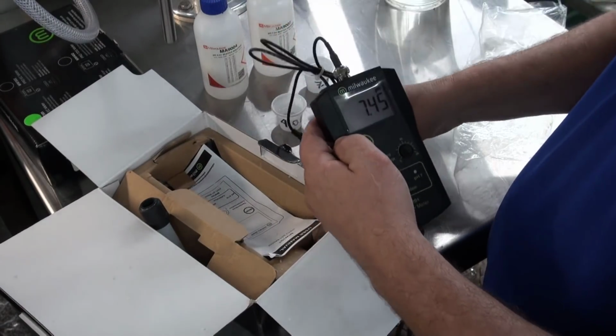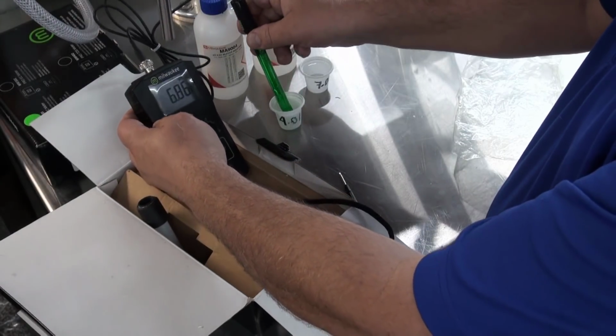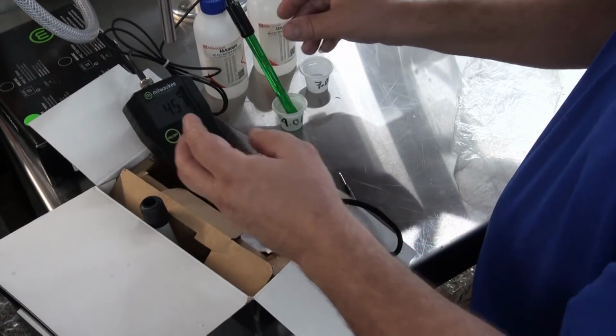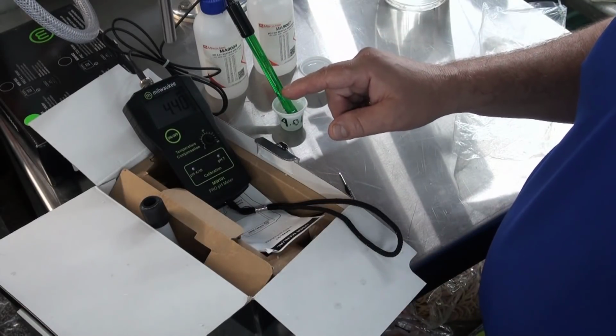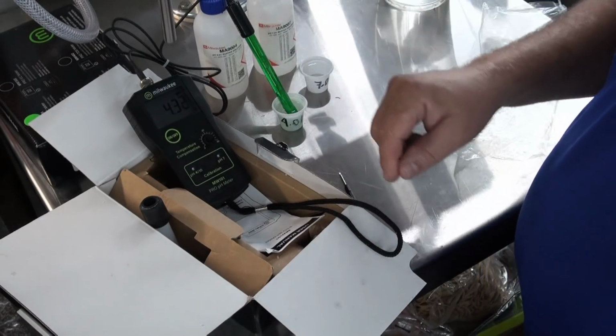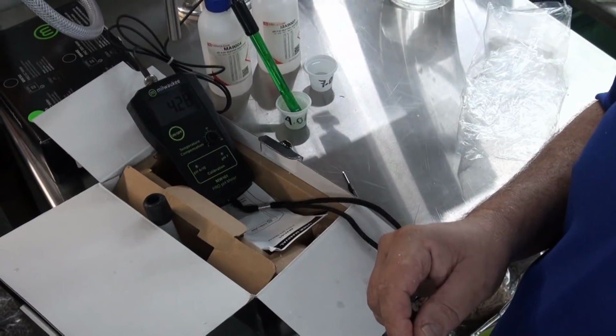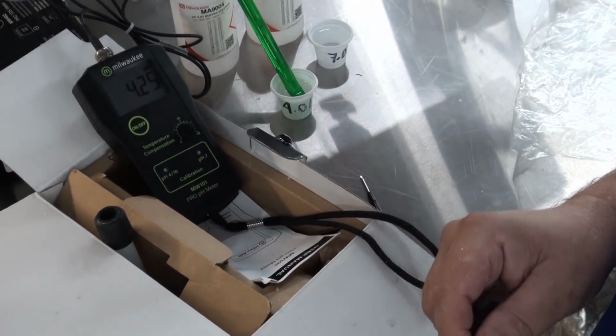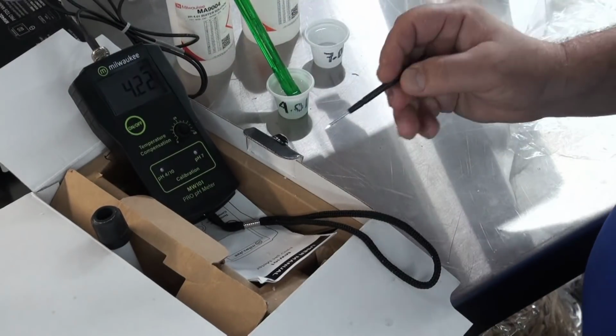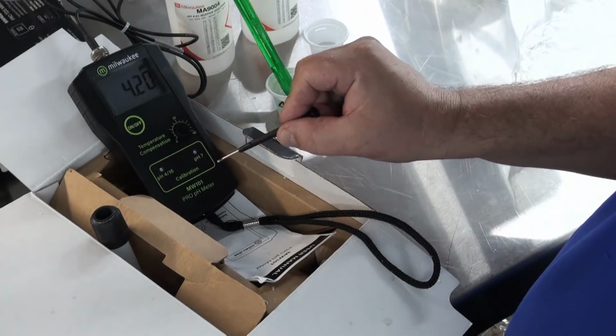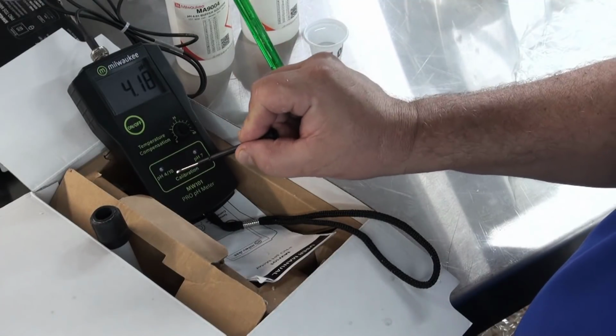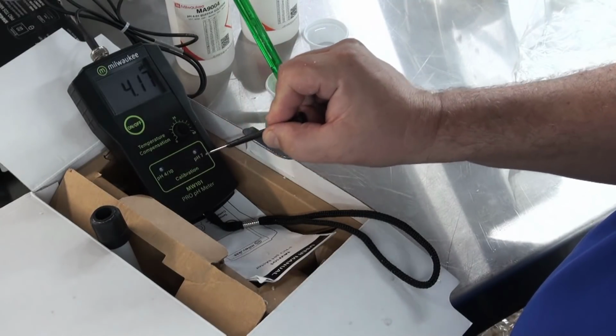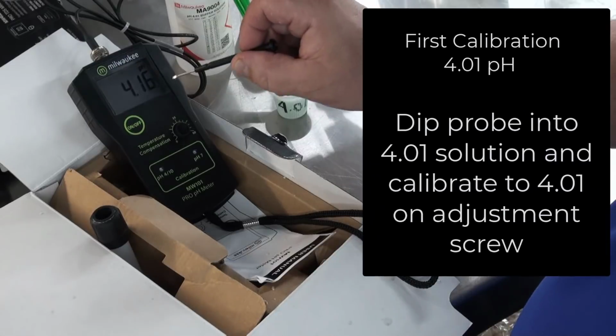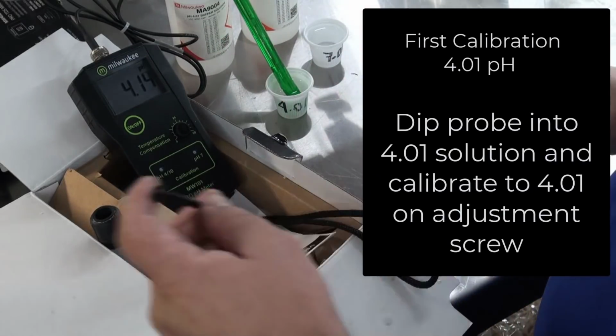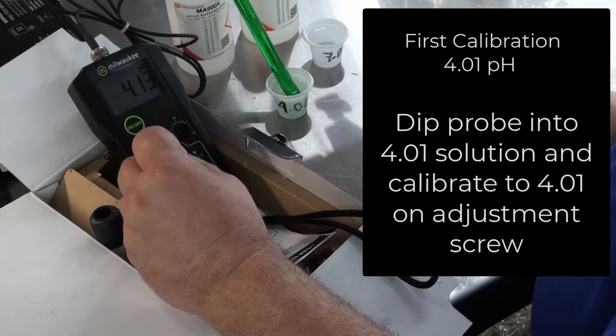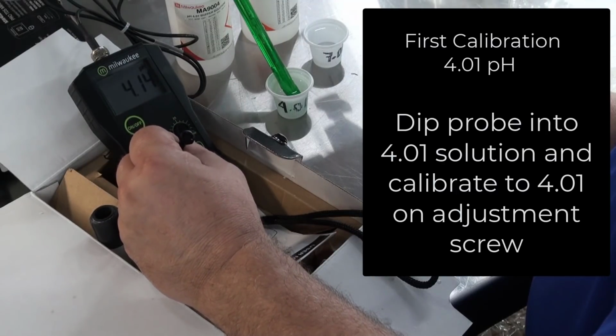So what we're going to do is basically stick the probe into 4.01, and you'll notice immediately on the display that right now it's going down into the 4s, okay, because it wants to calibrate. Now on the side of the unit itself, you've got a calibration of 4.01, calibration of 7. Now you can see it says 4.16 right there. All you have to do is stick the screwdriver into the 4 if you're calibrating 4 and turn it slightly.